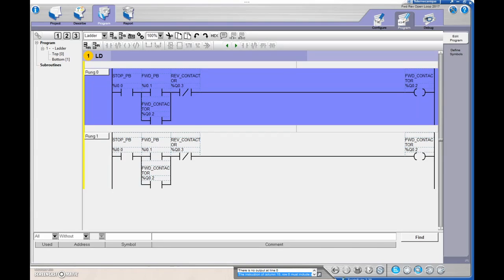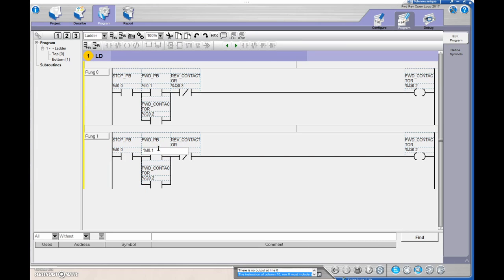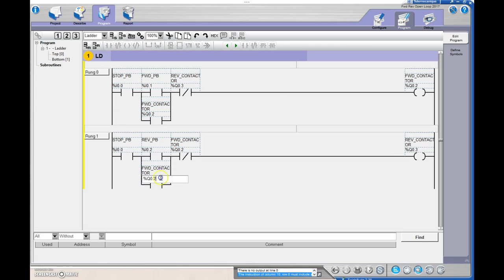Let's change those out. The stop stays the same. The reverse push button is input two. The forward contactor XIO is %Q0.2, making sure the forward contactor is off. Then the reverse contactor output is %Q0.3. We're monitoring that bit — nothing out in the field yet, just monitoring the bit so that when Q0.3 goes to a one, it provides another path of logic to turn on the reverse contactor.